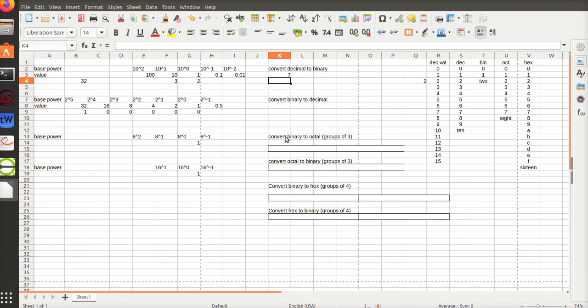And these are the common number systems. Now in binary you only have 2. You either have it or you don't. It's a 0 or a 1. It's a binary choice. What you see in PLCs is a lot of times things will be addressed in octal. Octal is base 8, which means there are 8 characters in octal. And we use 0 through 7, which are the same 0 to 7 we use in decimal, but we don't have an 8 and a 9 character in the octal numbering system.